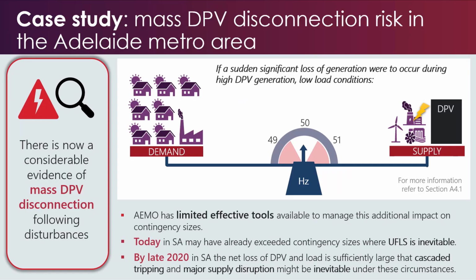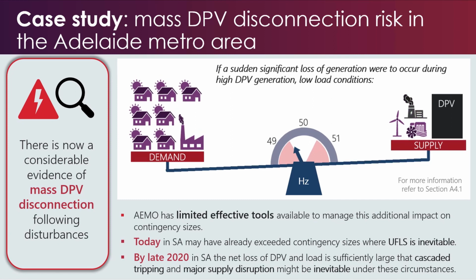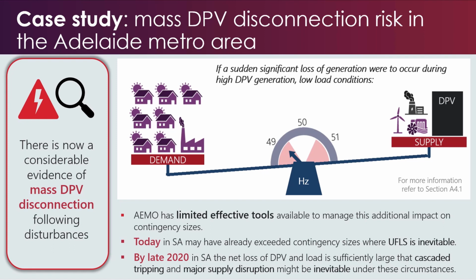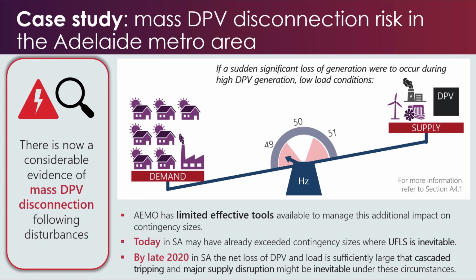So looking at the supply-demand balance again, now we're looking at a specific case study for an event in South Australia. Once again, the DPV is represented as a black box on the supply side. If there is a loss of a generator such as Torrens Island, which is near the Adelaide metropolitan area, and this in turn creates a resulting voltage event, we can see this loss of generator disconnect as it goes grey and the supply becomes lighter and the scales tip. In response to the transmission level voltage disturbance, we have found that up to 40% of DPV consequently also trips, as you can see as the black box becomes smaller. As a result, the scales tip even further than expected, so the DPV trip-off in fact exacerbates a supply-demand imbalance.